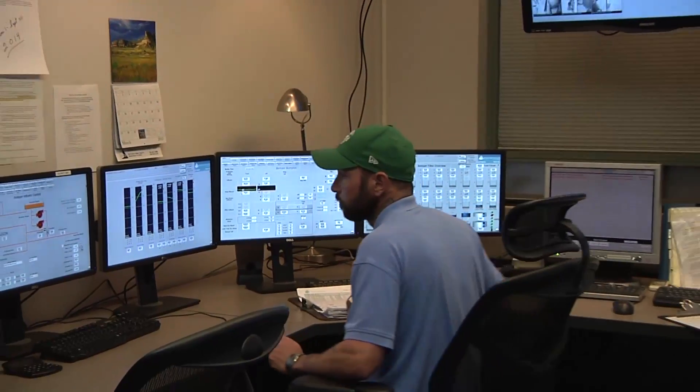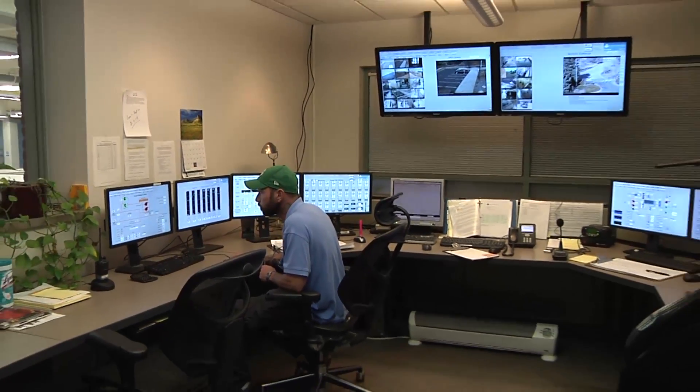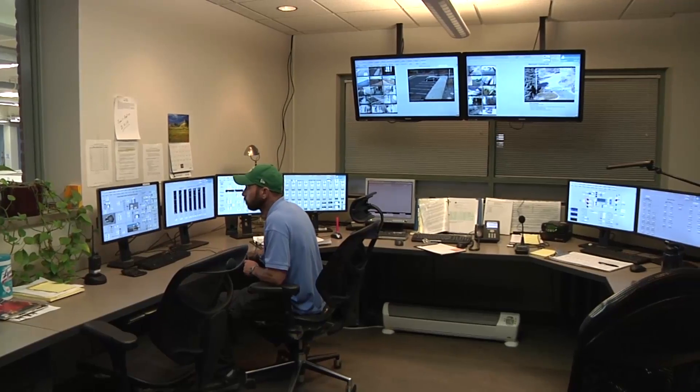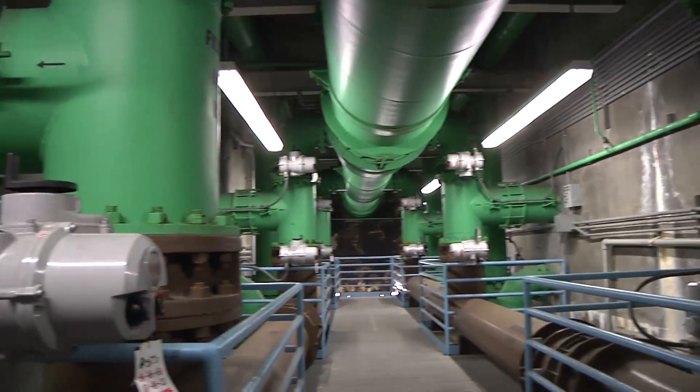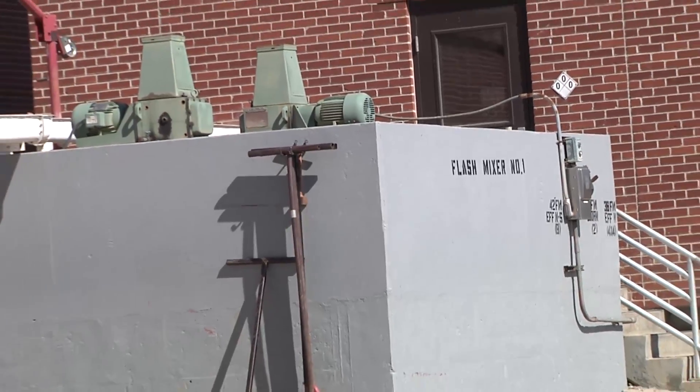The water comes into the plant through our raw water vault through two pipelines. This is actually two plants in one. The chemicals are dosed in sequence — we hit it with an oxidant, we take care of all tastes and odors and any metals that we want to get out of the water, and it comes into our flash mixers.